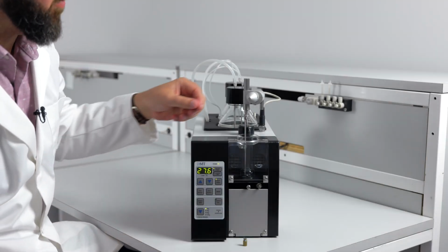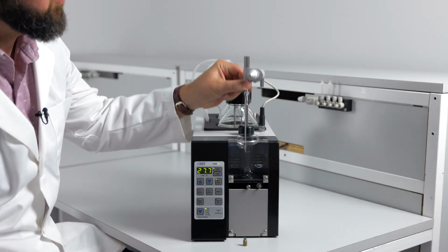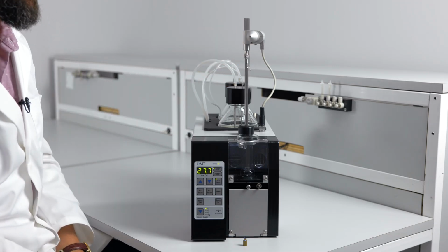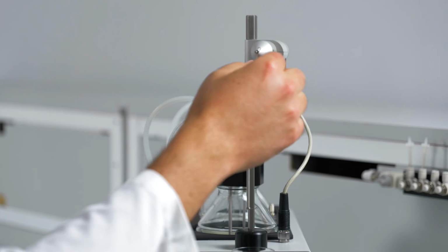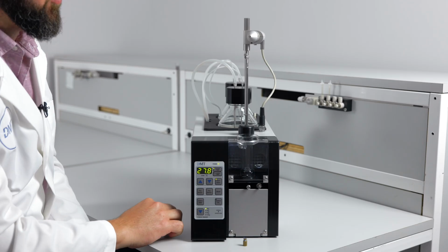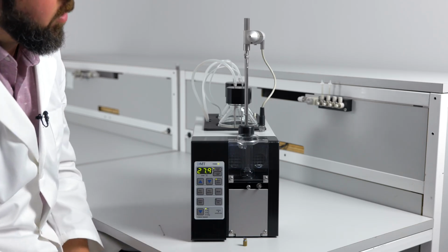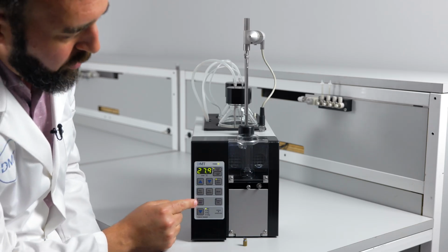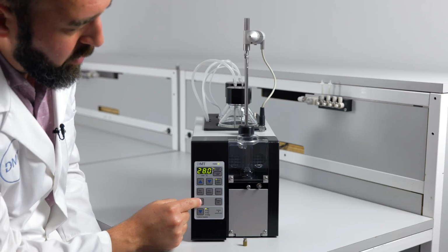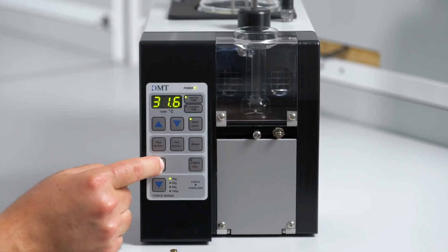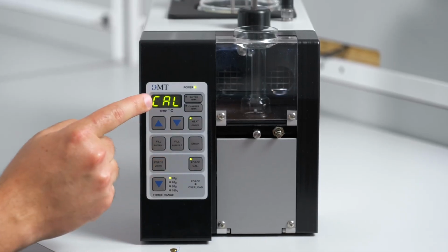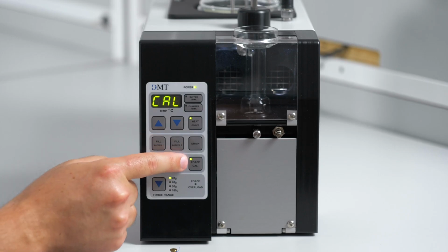In order to do the calibration, first you need to raise the tissue mounts out of the chamber. You need to remove whatever mount is on the transducer. Then we will hold force 0, or 0 force. Hold it until the light comes on for force calibration.